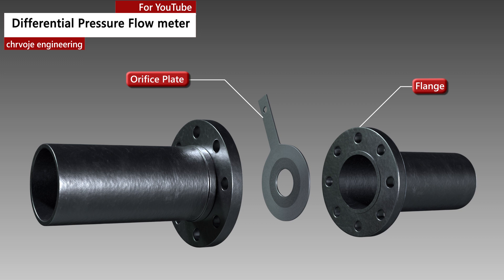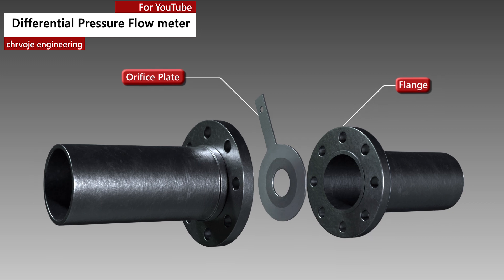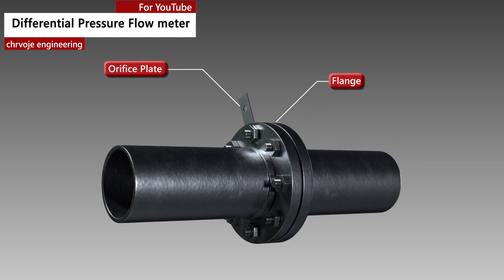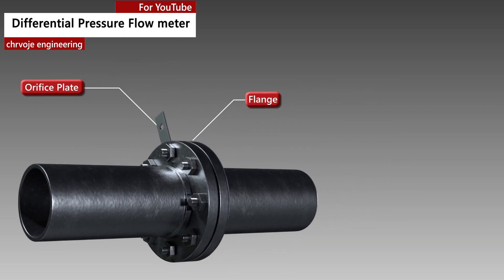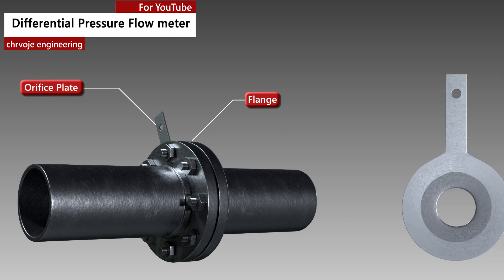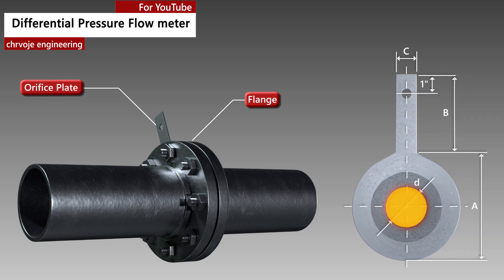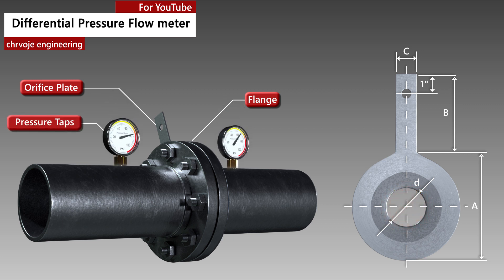The orifice plate is an in-line instrument that is installed between two pipe flanges. It is comprised of a circular metal disk with a specific hole diameter that reduces the fluid flow in the pipe. Pressure taps are added on each side of the orifice plate to measure the pressure differential.